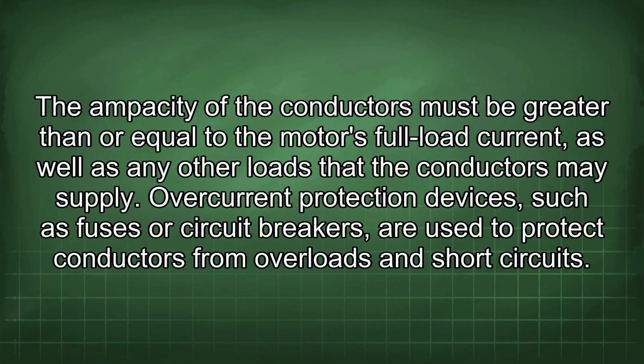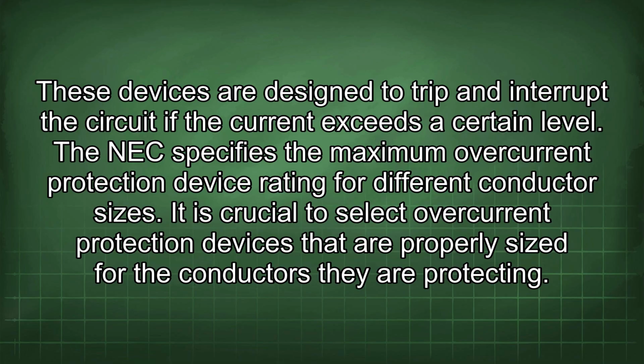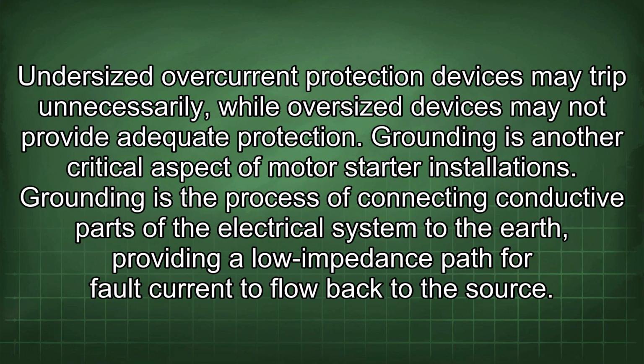Overcurrent protection devices, such as fuses or circuit breakers, are used to protect conductors from overloads and short circuits. These devices are designed to trip and interrupt the circuit if the current exceeds a certain level. The NEC specifies the maximum overcurrent protection device rating for different conductor sizes. It is crucial to select overcurrent protection devices that are properly sized for the conductors they are protecting. Undersized overcurrent protection devices may trip unnecessarily, while oversized devices may not provide adequate protection.